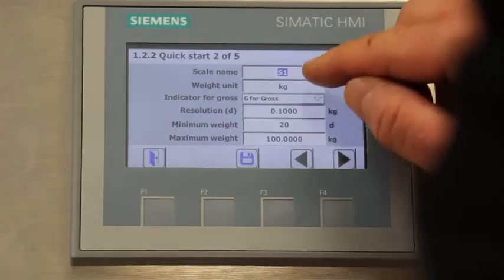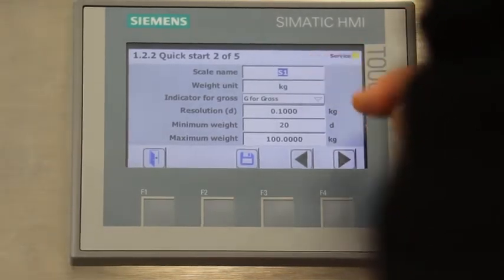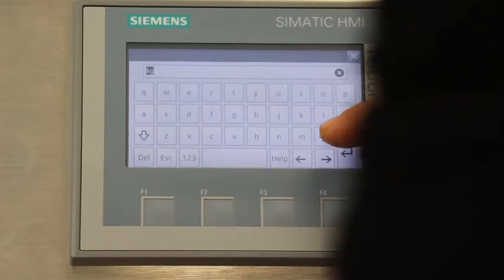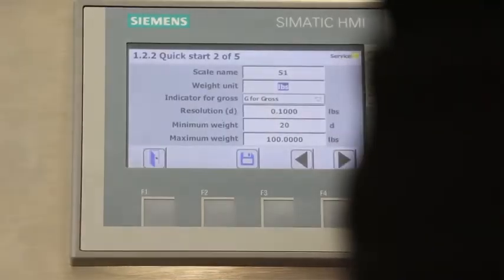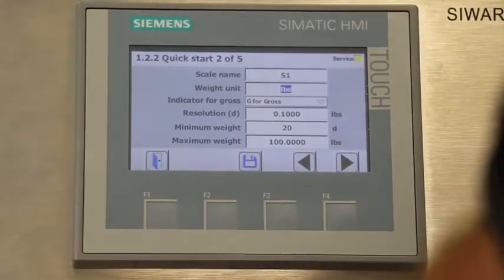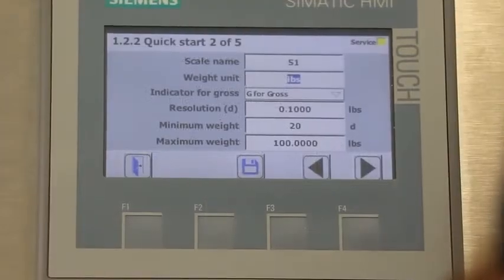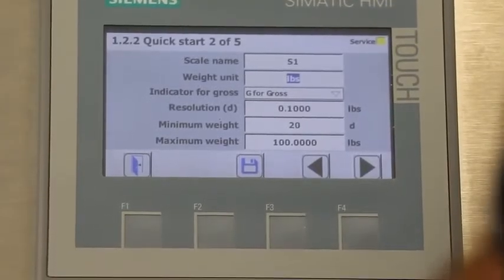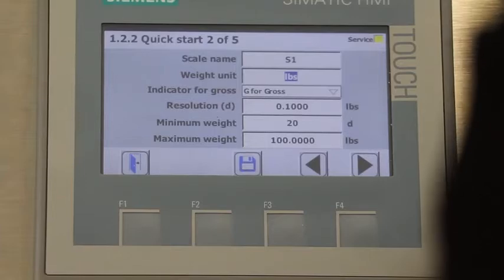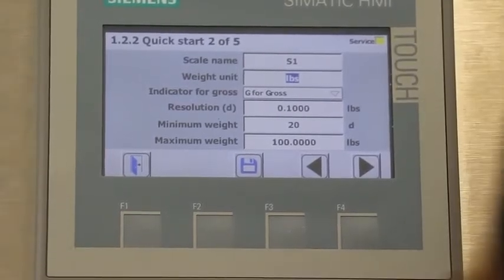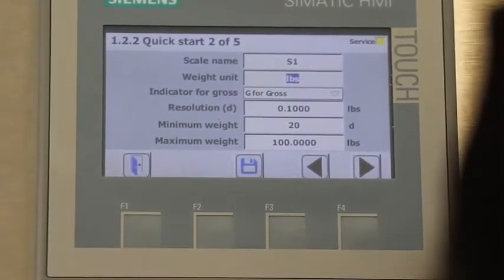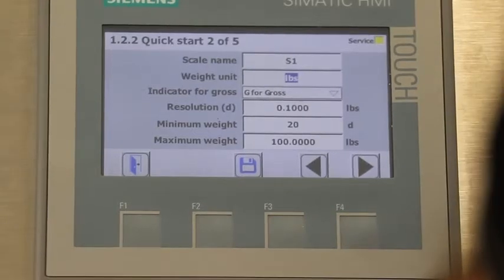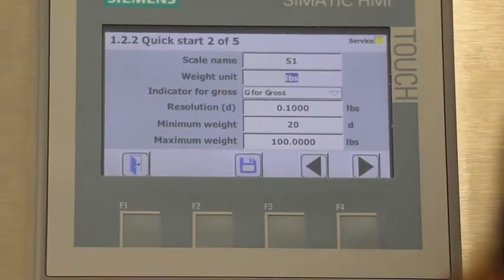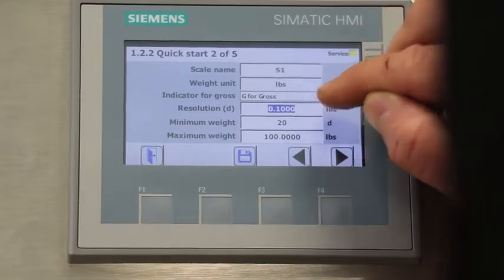The next field is the measurement units. We'll enter pounds for this application. The next field is the indicator for gross. In the US, G is almost always used as an indicator for gross. So we'll leave that as a G. The next field is the scale resolution. This will be the smallest increment the scale will display. So we'll change that to 0.001.